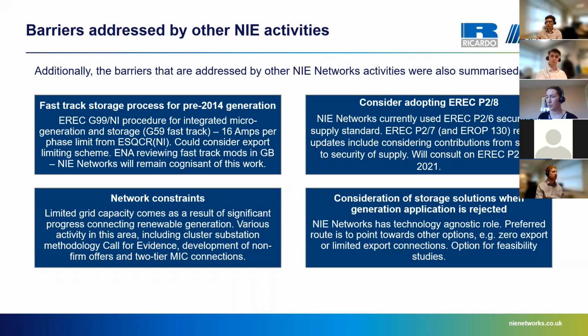Looking at network constraints, which we've talked about, there's various activities in this area within NIE Networks, including a review of the cluster substation methodology, development of non-firm offers, and development of two-tier maximum import capacity connections. Looking at the security of supply standard, NIE is following an ENA working group on this, which they're currently finalizing changes to the latest version of this standard, P2/8, and the ENA will then consult, and subsequently NIE Networks will consult on that and consider adopting that standard.